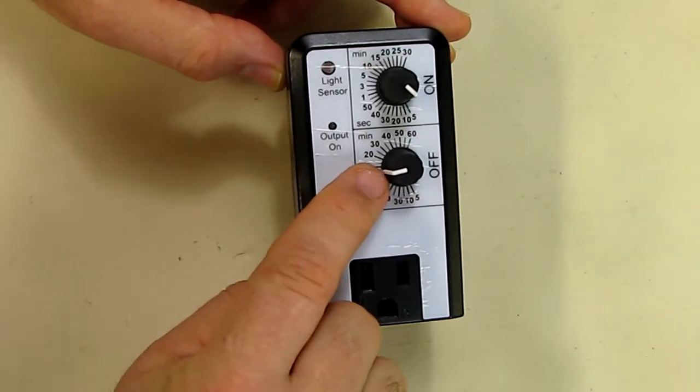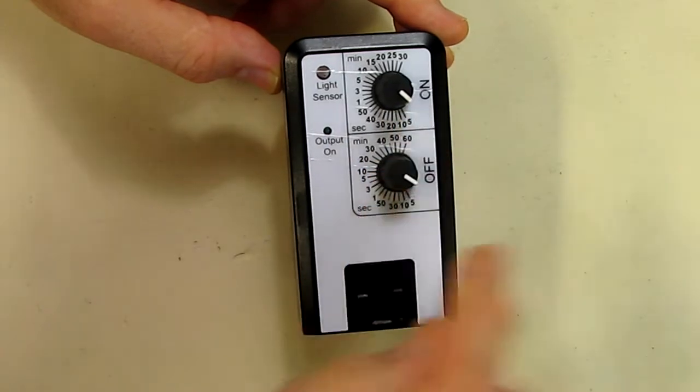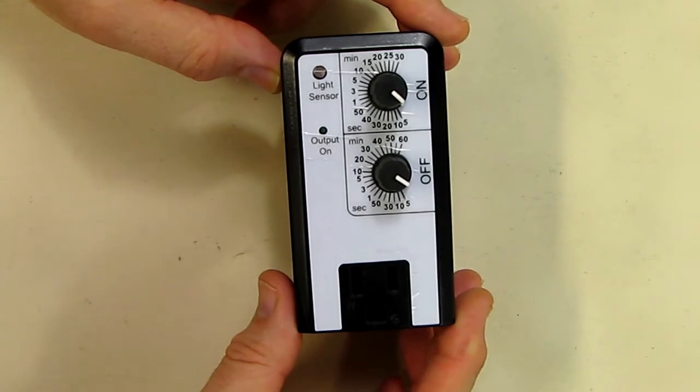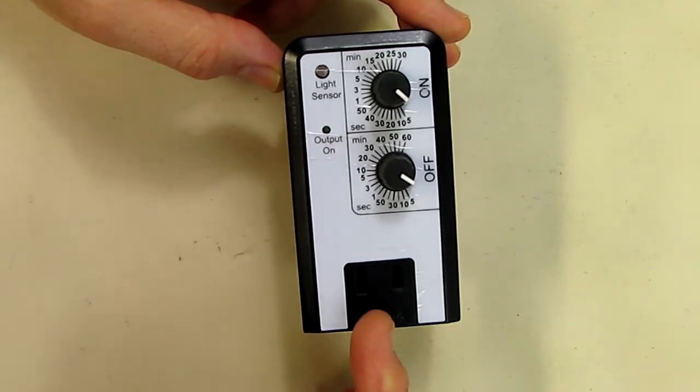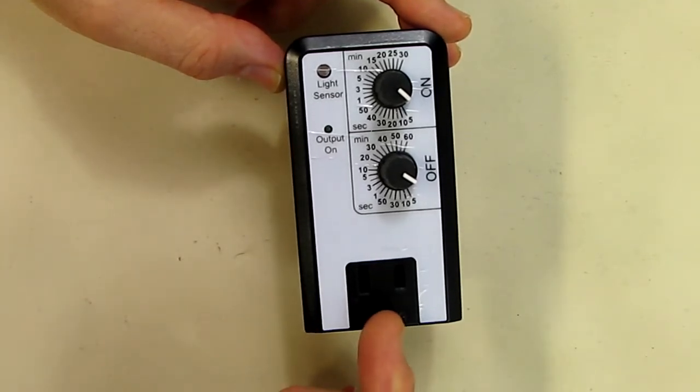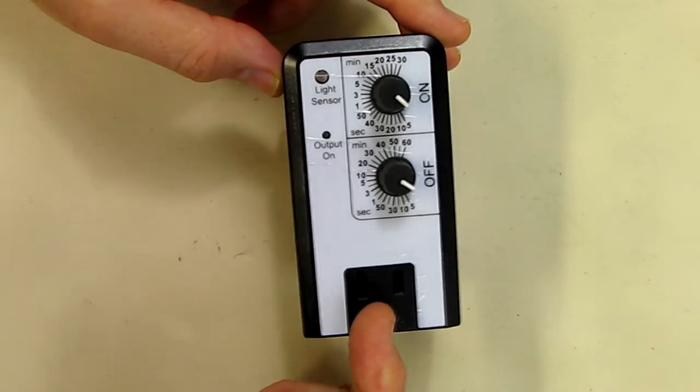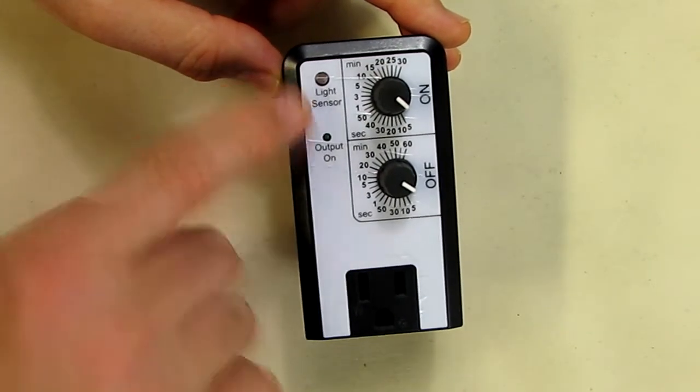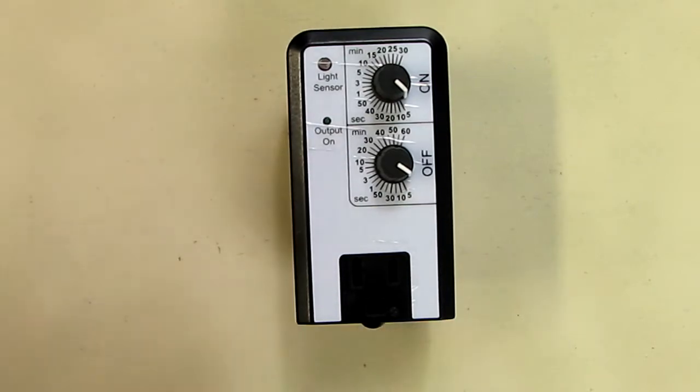The output LED comes on when this thing supplies the switch. It's 15 amp power, can run up to one horsepower motor. You notice there's a light sensor right there, that's to determine daylight versus night and we're going to test that function now.